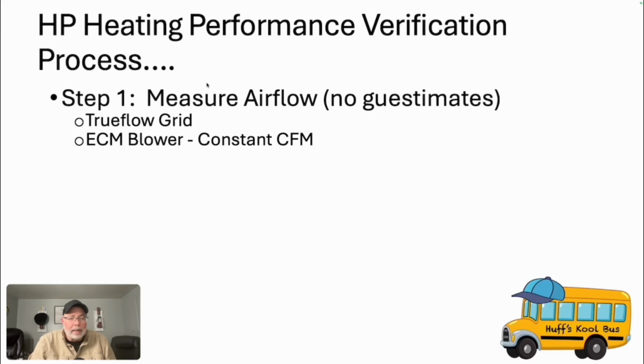Remember, ECM blowers kind of come in what I like to say two flavors. You have your constant CFM, and these are the variable speed blowers where you set the CFM, whether it's through a communicating thermostat or whether it's dip switches on the board, things like that. And then that blower is going to ramp up against the static to deliver that airflow. Now, the second flavor of ECM blowers are what we call constant torque. And as the static is increased, that blower will slow down, kind of like a PSC motor, but not near as bad. But that motor, you can't use this on.